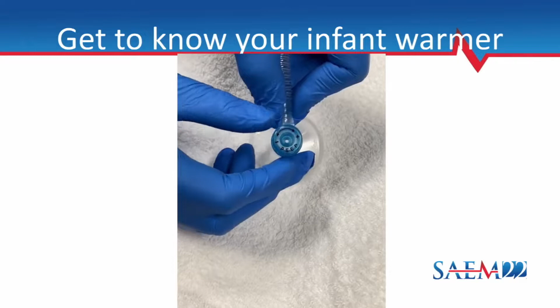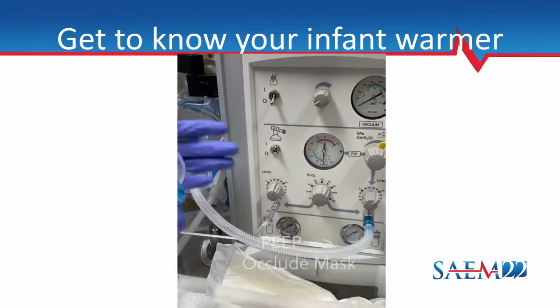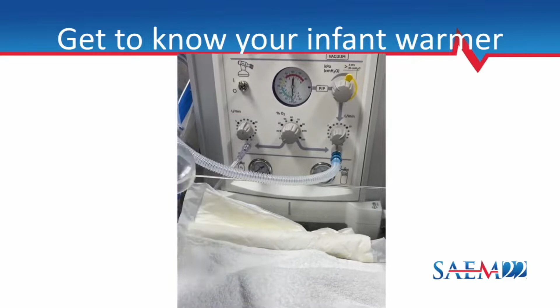The PEEP is adjusted on the T-piece, which is this piece of equipment that you see here, by adjusting the knob on the top. And then when it comes time to give breaths, you can assess your PEEP or your CPAP by occluding the mask with your hand and seeing what pressure you get on the manometer there. And as soon as you occlude the top hole of your T-piece, you're actually delivering a breath. That's going to show you what your positive inspiratory pressure is and help you adjust your pressures from there.